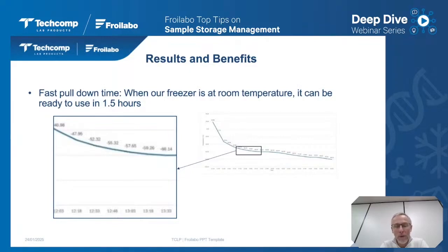But when you have a backup unit turned off, and you have a technical issue on another unit, and you have to transfer all the samples of the defaulted unit to the backup, you need the backup unit to reach the temperature very fast. And we measured that with our improvements. Now our equipment needs only 1 hour and 30 minutes to reach -60 degrees.